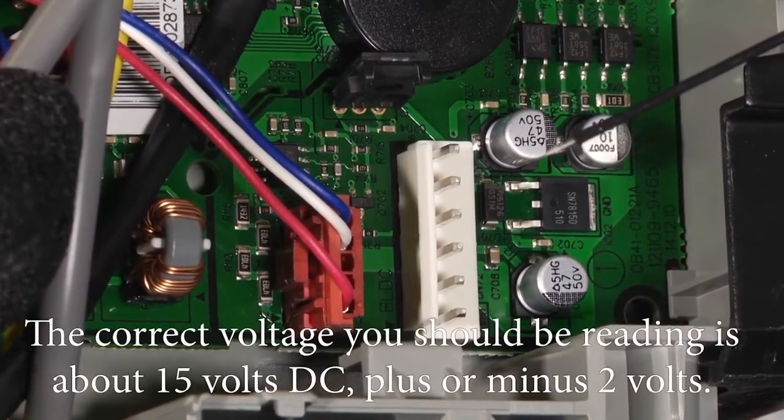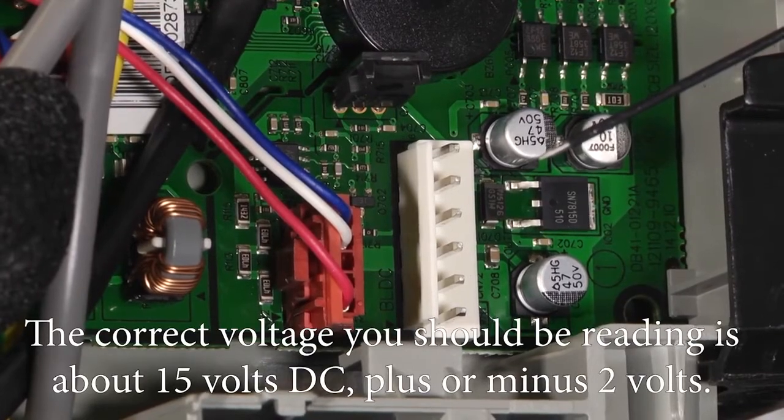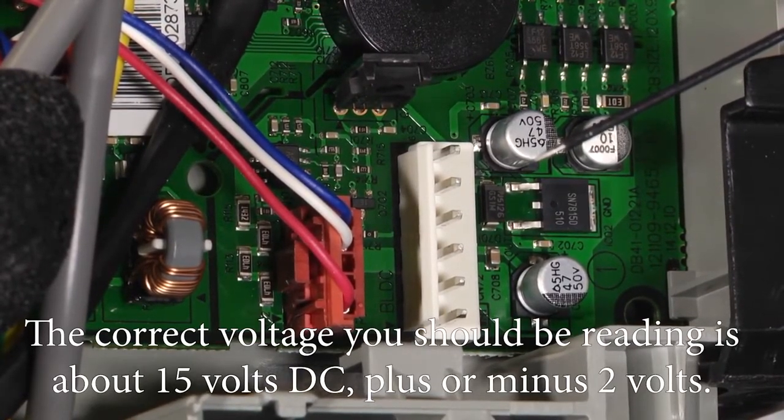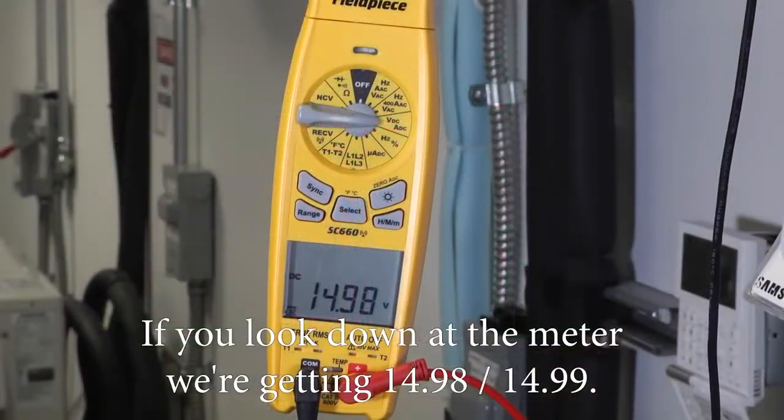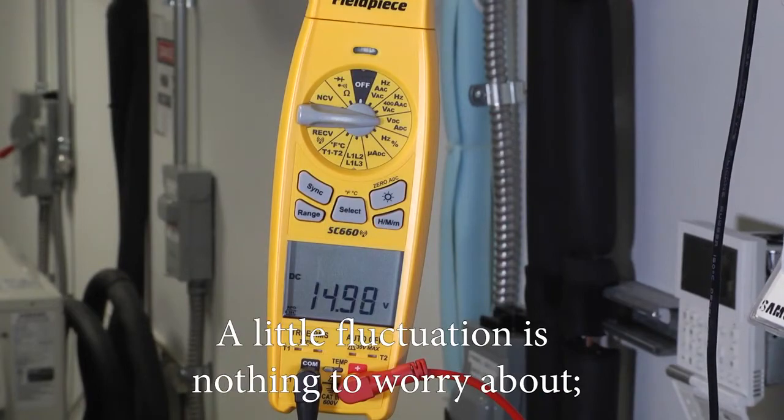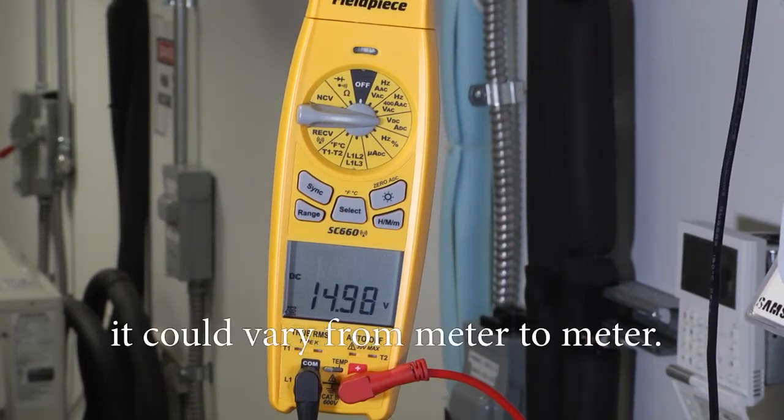The correct voltage you should be reading there is about 15 volts DC plus or minus two volts. If you look down at the meter, we're getting 14.98-99, a little fluctuation—nothing to worry about. It could vary from meter to meter.